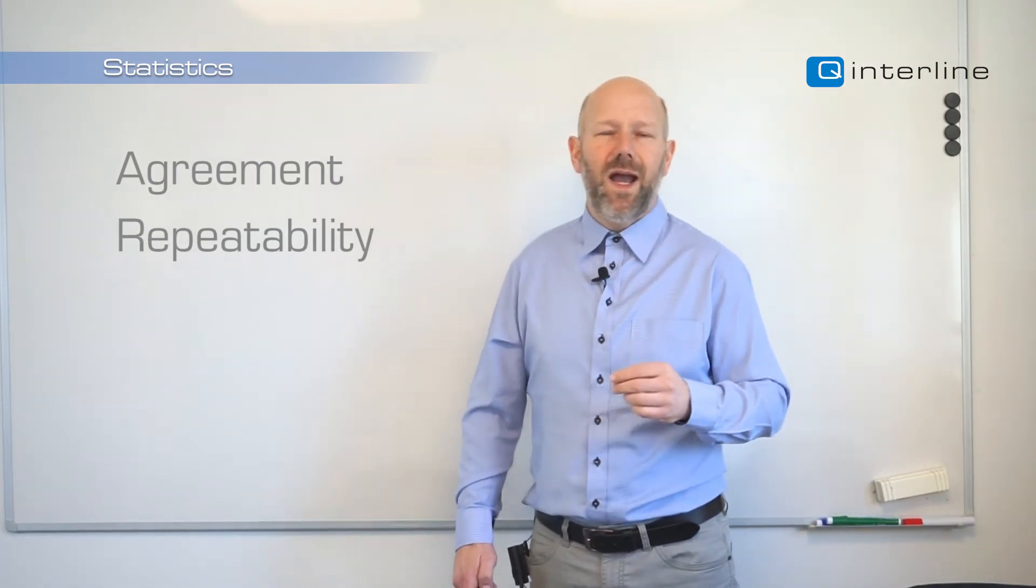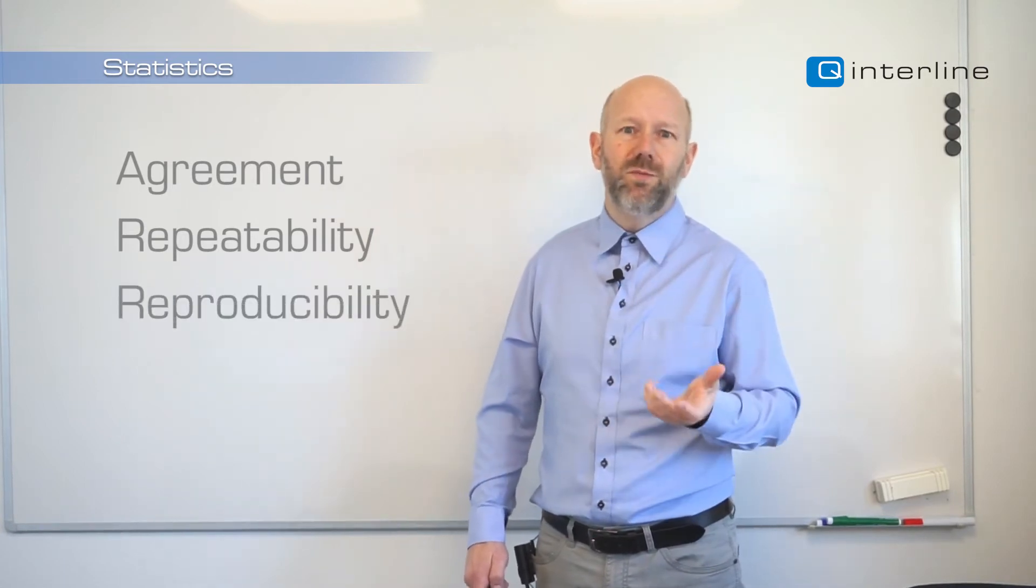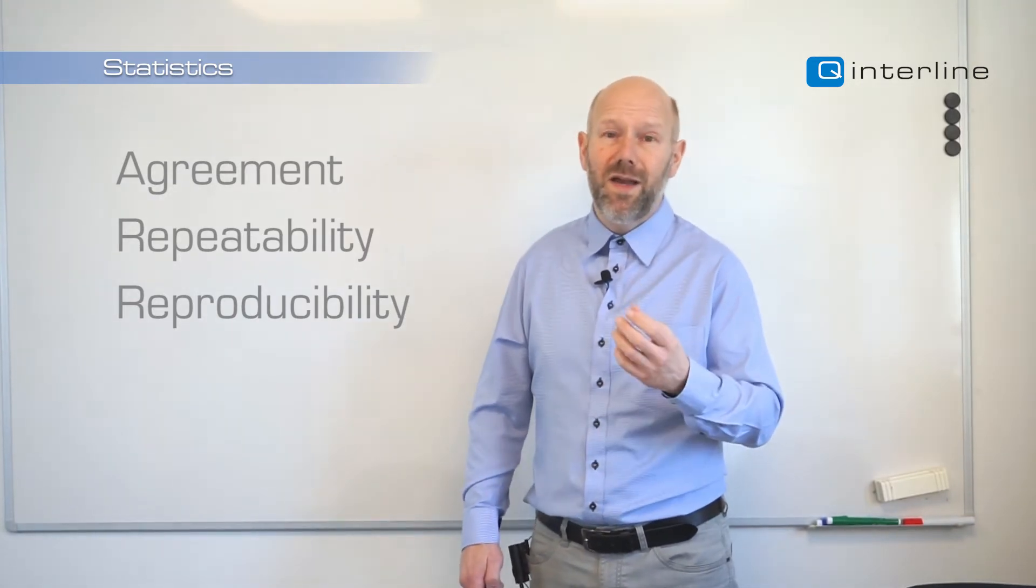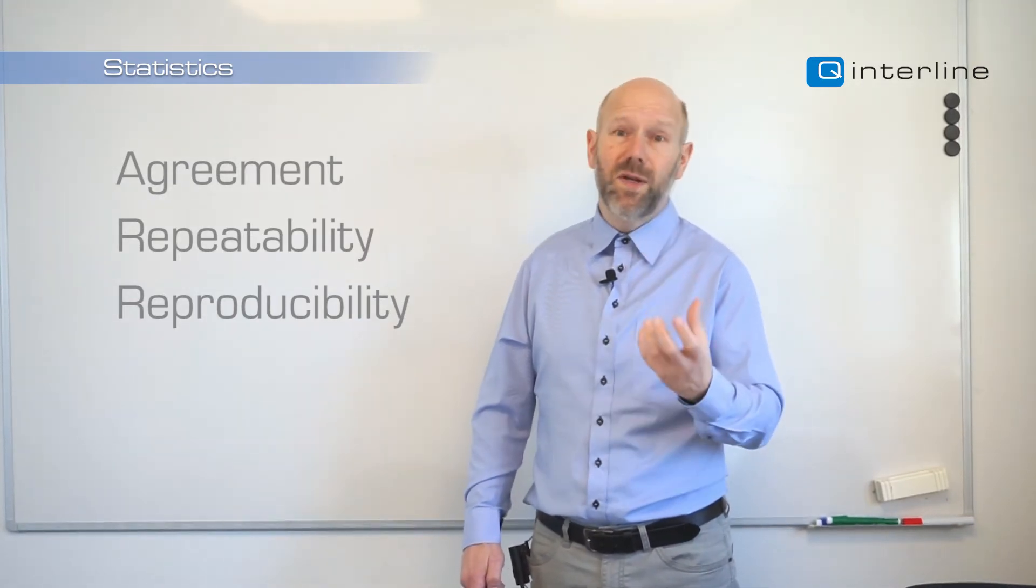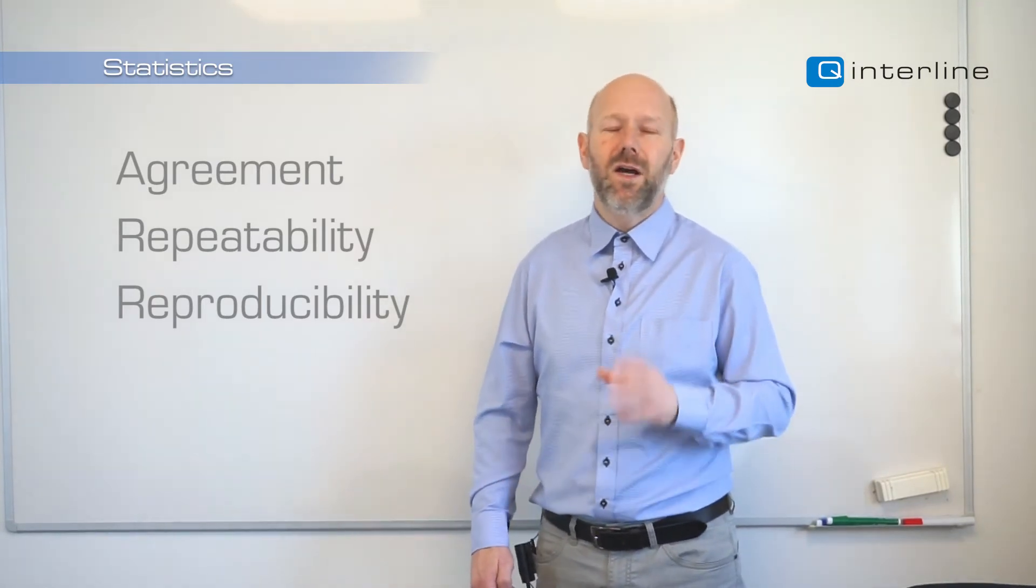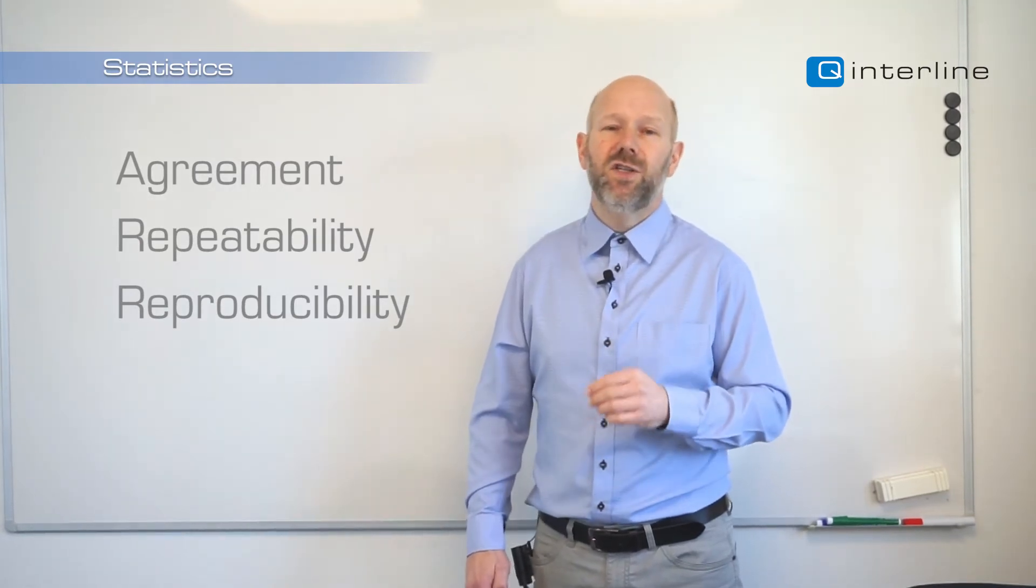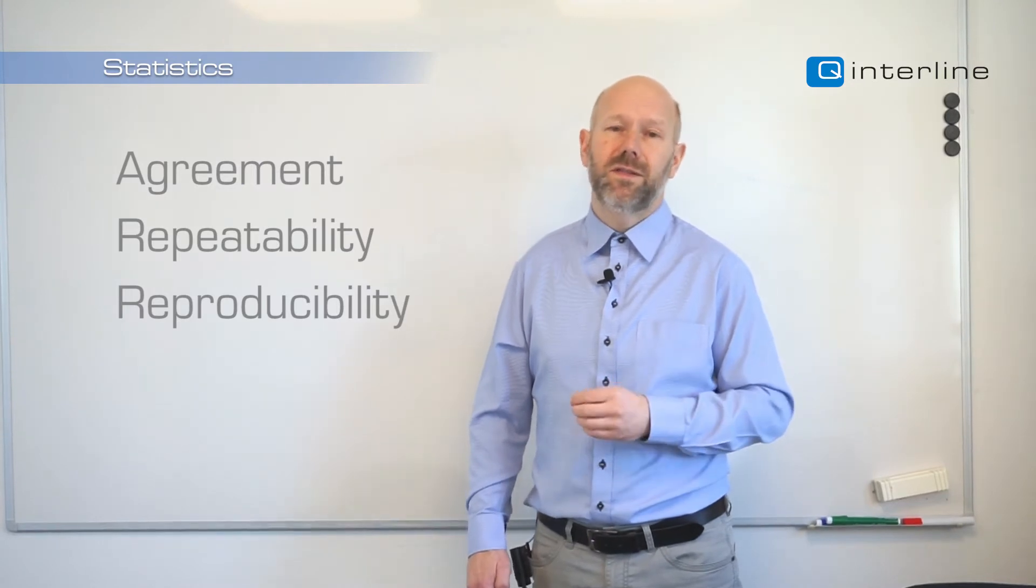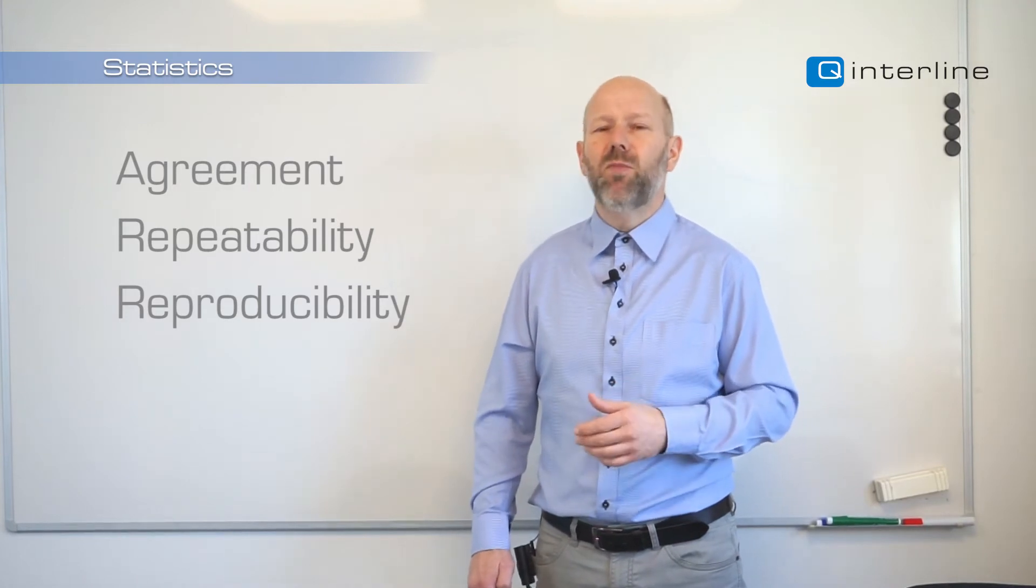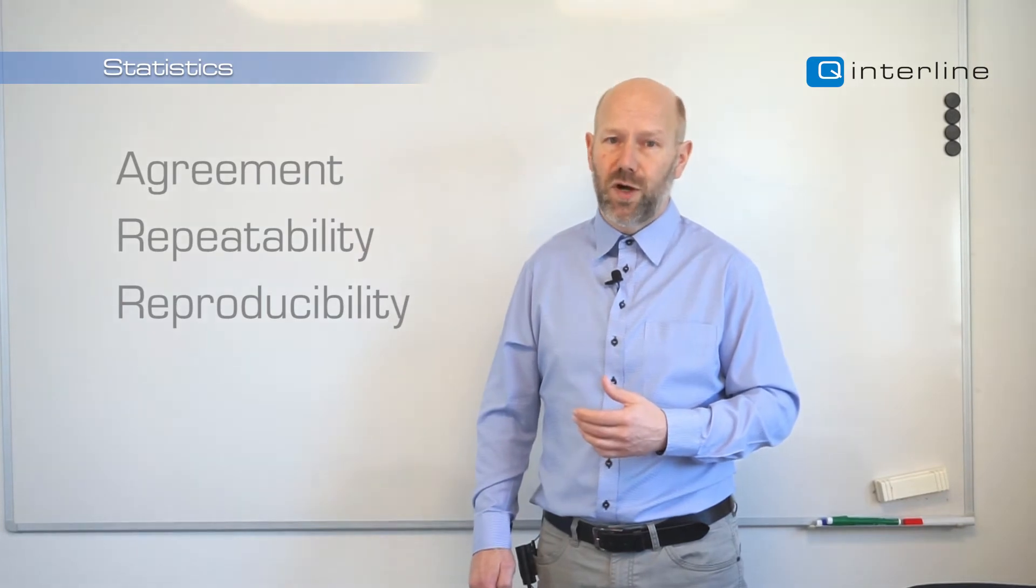Then short-term robustness is also another word for repeatability. Slightly longer term, this word is also called reproducibility. That will mean if another guy took the same sample or similar sample to a similar analyzer tomorrow in another lab, would he get on the decimal the same number? No. But what kind of deviation may I account on from this analyzer given this reproducibility? So these questions are important to answer before we start using such an analyzer for production.